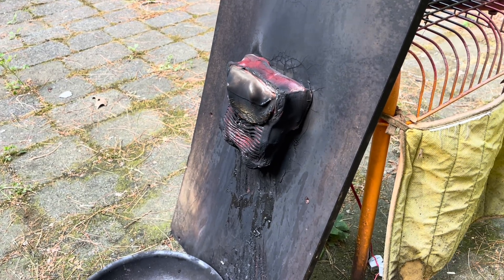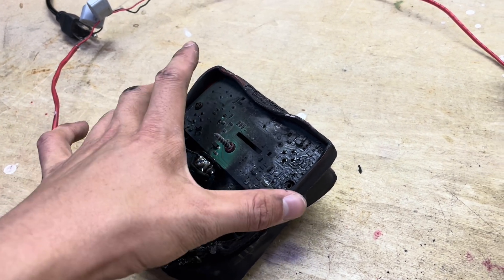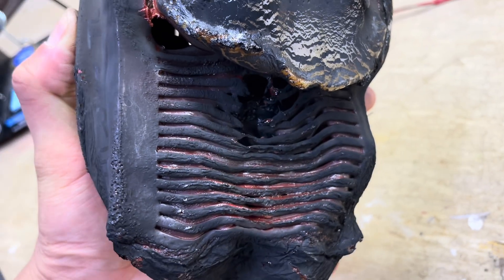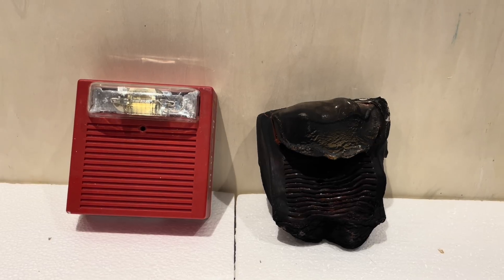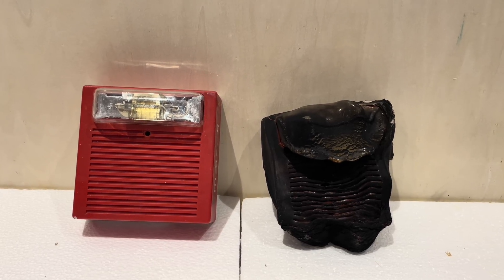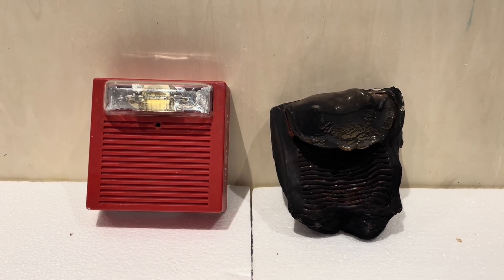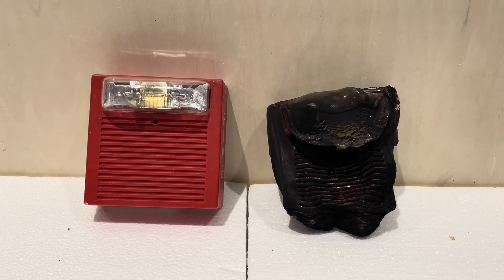I don't think it's recovering from this one, but you never know — always got to give it a try. Alright guys, you're not going to believe this, and I know I've said that so many times. I just took it inside because the test was over — and check this out: the strobe is partially functional and the horn is still functional. Unbelievable. Well, that's going to do it for today. That's what it takes to kill — or at least partially kill — a Wheelock AS horn strobe. The fact that this thing is still partially functional is actually mind-boggling, especially after it was on fire and died multiple times. I think the overcurrent or overheating protection inside is what kept it going — every time it sensed it was getting too hot it would shut off, and then after it cooled down it would start going again. But that is very, very impressive. Thank you for watching and take care. Bye bye.